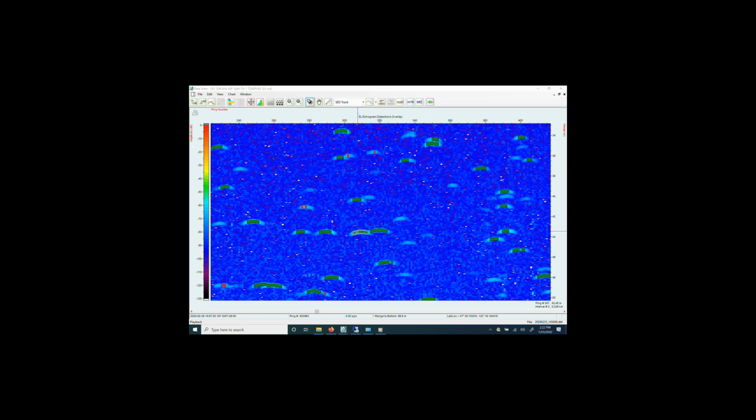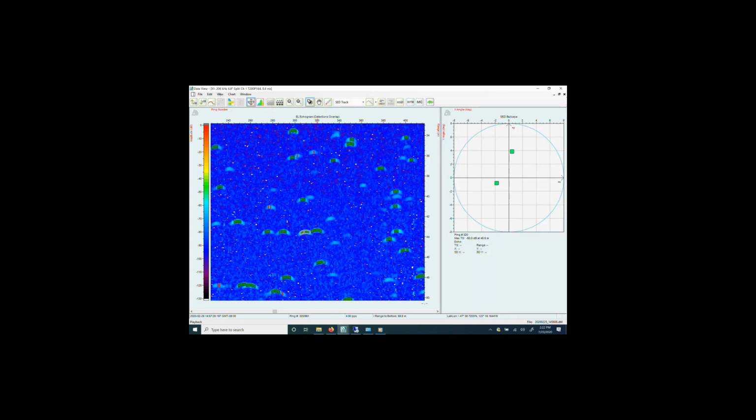To see the individual SED tracks in more detail, we can open the Bullseye graph by clicking on the Bullseye button here. The Bullseye graph shows an overhead view of the transducer beam and displays where the detected echoes are in X and Y phase angles. Each echo looks like a small arrow that points forward into the time domain, and echoes in SED tracks will be connected by a thin line.